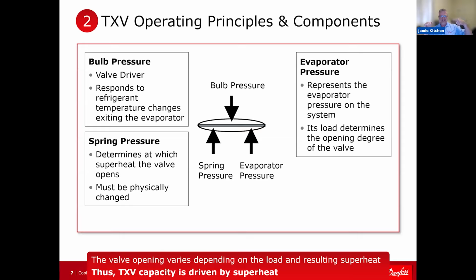All right. So if you look at a TXV, it's got an arrow on it on the side. That's your primary flow direction for what you want to use it. So on the outlet where that arrow is pointed, that's your evaporator. So even though the refrigerant's flowing out of there, it is at the pressure going into the evaporator. It could be before your distributor. It could be if there's no distributor, and we'll talk about that in a second. But that's the force under the diaphragm that sits in that power head. That's one. Second one is your spring pressure.